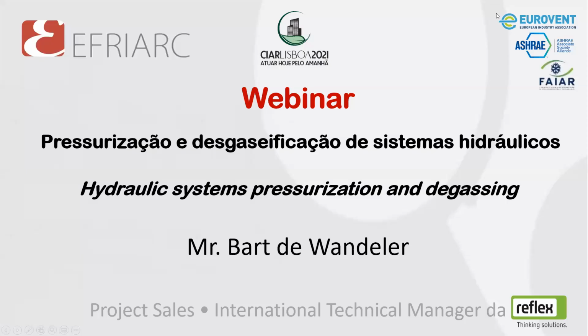One small question: imagine you have a small apartment, 80 or maybe 100 square meters, where the boiler is located in the kitchen cabinet, and you have a condensing boiler because you have an underfloor heating system with plastic pipes. You have oxygen migration into the system, and with aluminum condensing boilers, oxygen is poison for the boilers. So what's your advice so we can avoid corrosion of the boiler body due to oxygen migration from the pipes? Is the expansion vessel enough, or should we use some active protection?